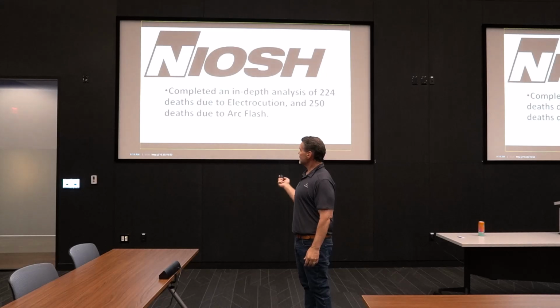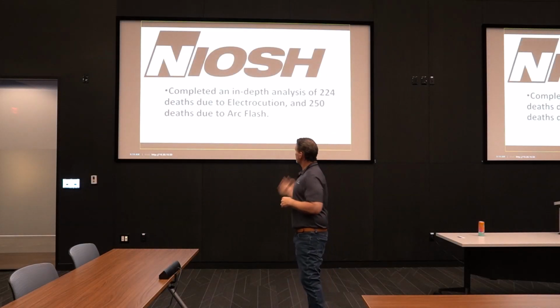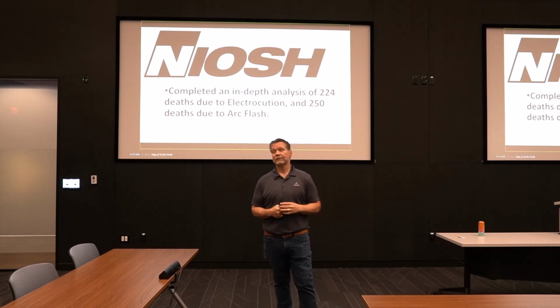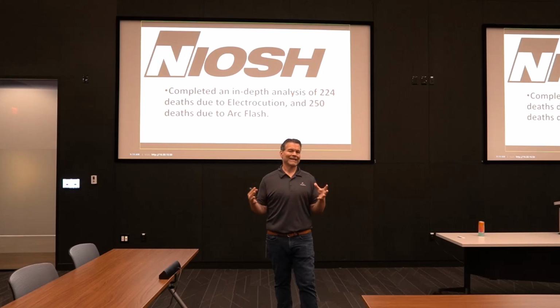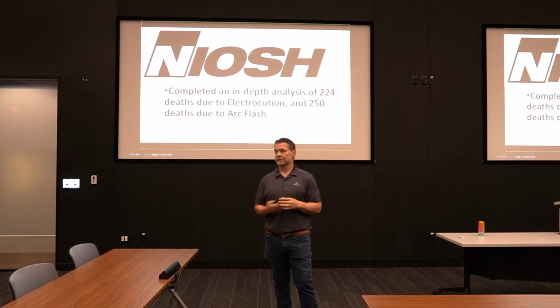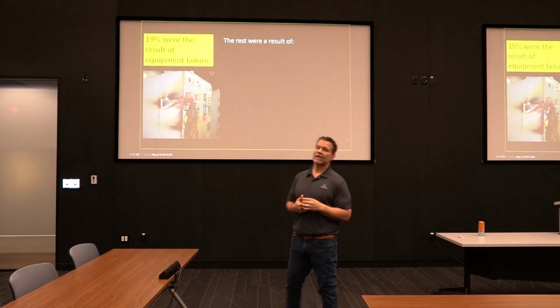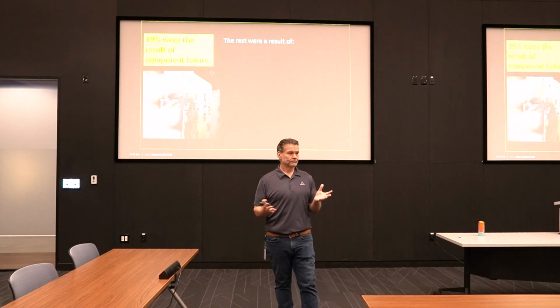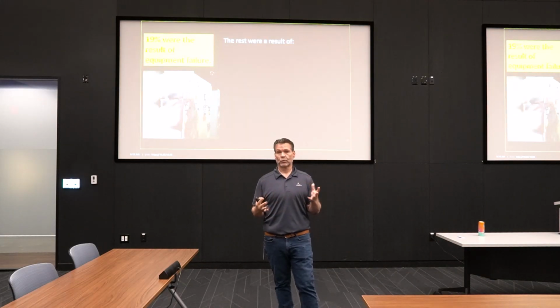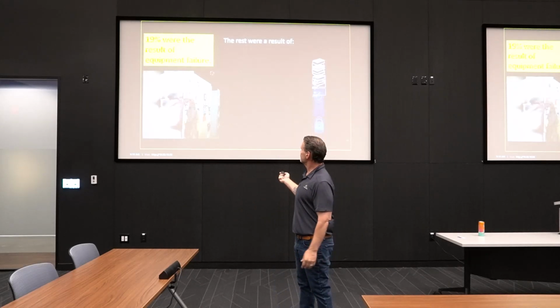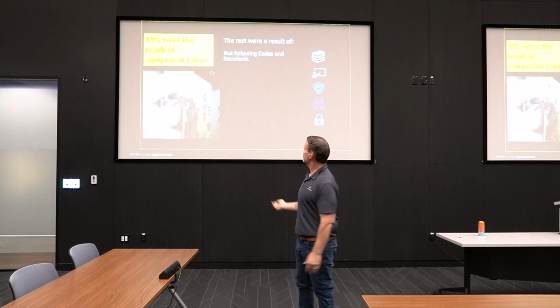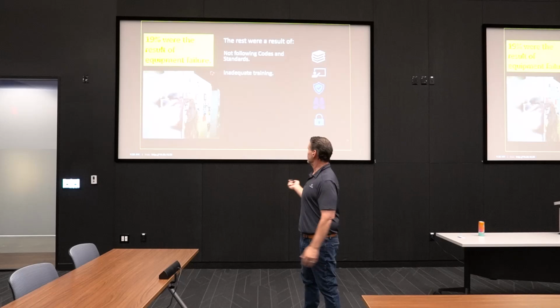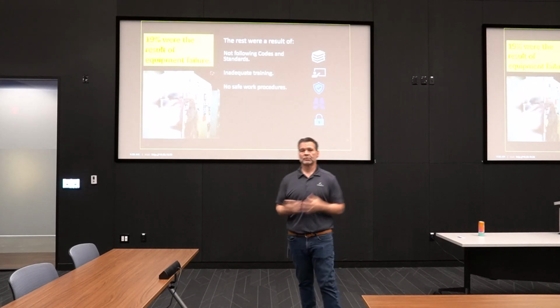So NIOSH did a study of 224 deaths due to electrocution and 250 deaths due to arc flash, trying to figure out exactly what went wrong that caused these fatalities. And what they found was that 19% of the time it was equipment failure. That's a pretty low number, right? 19% of the time. That leaves 81% of the time where something else went wrong. And what they're actually finding was: not following codes and standards, inadequate training of employees and supervisors, no safe work procedures done whatsoever, no pre-task work plan, no job hazard analysis, things of that nature.